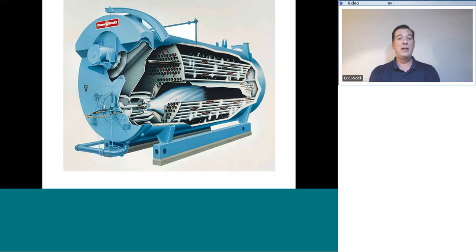That is why in this particular type of burner, when the blower is simply blowing air into the heat exchanger, it is slightly positive pressure. As soon as the fuel is introduced and combustion is initiated, that positive pressure goes to negative pressure. Now the fan's only purpose is to supply the air for that combustion process. And once it happens, the whole flue ways inside of this boiler becomes negative pressure, and that flue product is now drawn out of the boiler just as it was before. It's wild. It's weird. And until you see it happen with a pressure gauge on it, you wouldn't believe me, but it's there. So at the flue, on all of these power burning appliances, the outlet of the heat exchanger is a slight negative pressure. Now, this is not extremely negative. It's very slight. It's about a minus 0.02 inches of water column, but it is negative, and it does pull through the appliance. Pretty neat stuff.